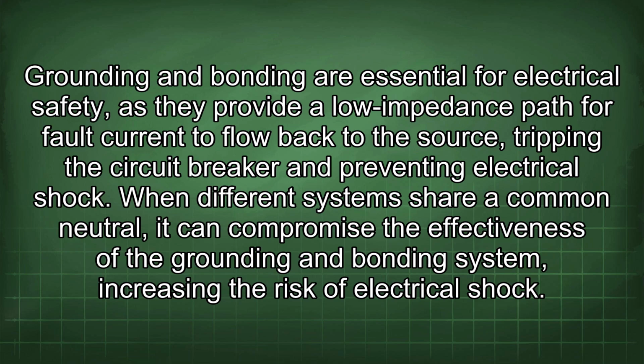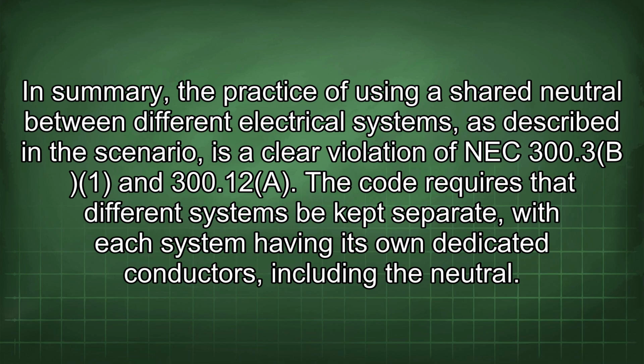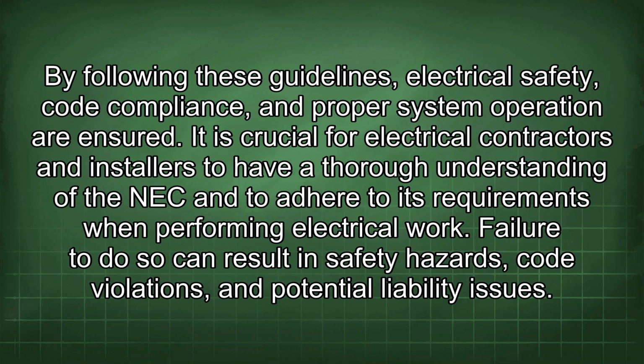In summary, the practice of using a shared neutral between different electrical systems, as described in the scenario, is a clear violation of NEC 300.3(B)(1) and 300.12(A). The code requires that different systems be kept separate, with each system having its own dedicated conductors, including the neutral. By following these guidelines, electrical safety, code compliance, and proper system operation are ensured. It is crucial for electrical contractors and installers to have a thorough understanding of the NEC and to adhere to its requirements when performing electrical work. Failure to do so can result in safety hazards, code violations, and potential liability issues.